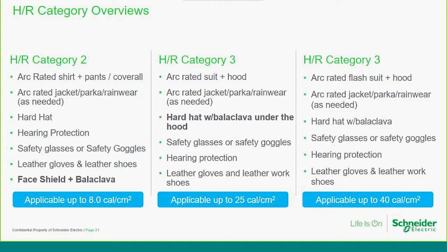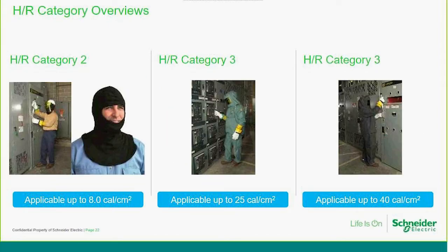And as we go even further, we need a full rated arc flash suit plus hood, plus the jacket. The more layers of clothes put on, the better effectively your ability to absorb those levels of energy. And so the categories keep going higher and higher and higher. But after 40 cal/cm2, you're really on your own. You really need to think about trying to mitigate and reduce those values of energy that's in there. So again, just some basic examples there of the types of clothing we're talking about.